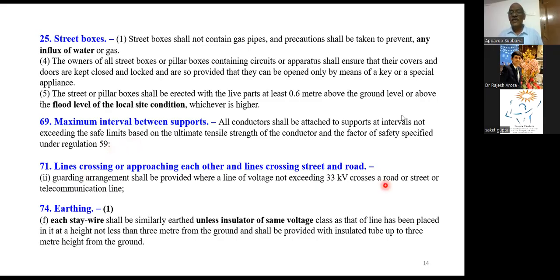So these are purely mechanical and civil factor of safety calculations using ultimate strength. This should be strictly followed. And while a line is crossing or approaching, crossing a street or road, what is the arrangement? Guarding shall be provided where the line voltage does not exceed 33 kV. So for all lines up to 33 kV, you have to provide it. Have we not seen such conductors which are not guarded? It is there. So these are things that any citizen can learn and raise his concern to the authorities concerned so that it can be rectified.